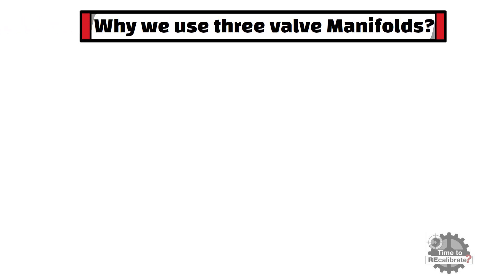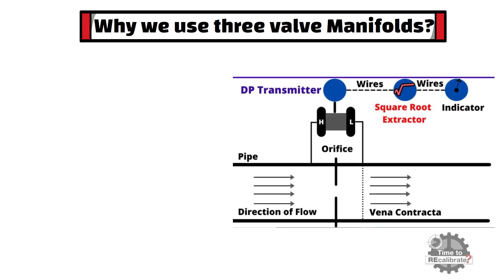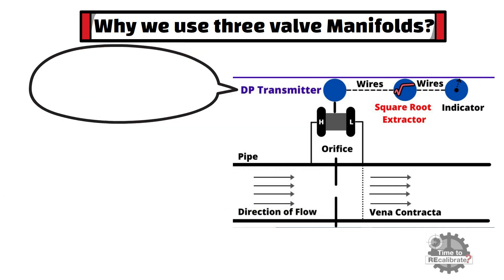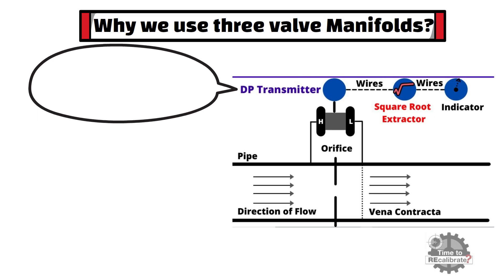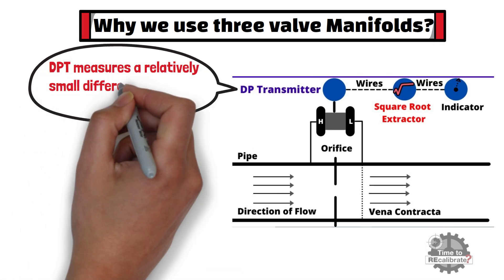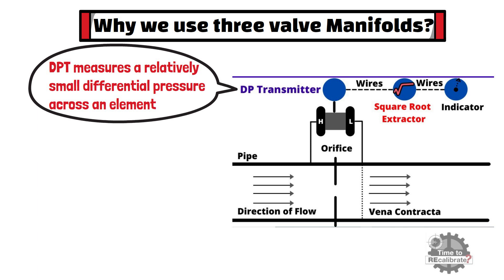First of all, let's learn what will happen to differential pressure transmitter if we do not use three valve manifolds. One of the problems with the use of differential pressure transmitter with respect to the measurement of flow is that the transmitter measures a relatively small differential pressure across an element such as an orifice.